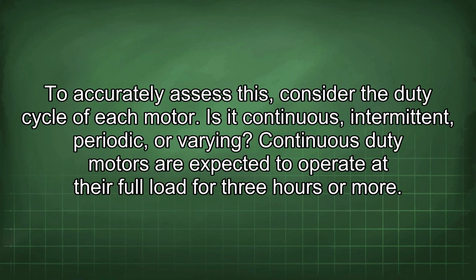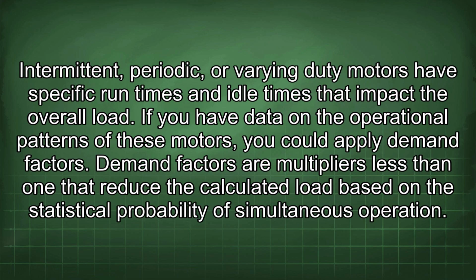To accurately assess this, consider the duty cycle of each motor. Is it continuous, intermittent, periodic, or varying? Continuous duty motors are expected to operate at their full load for 3 hours or more. Intermittent, periodic, or varying duty motors have specific run times and idle times that impact the overall load. If you have data on the operational patterns of these motors, you could apply demand factors. Demand factors are multipliers less than 1 that reduce the calculated load based on the statistical probability of simultaneous operation.